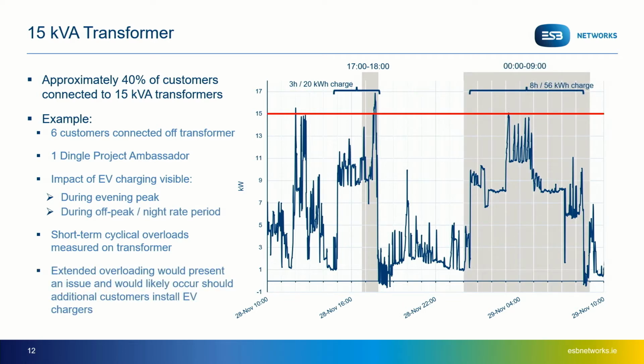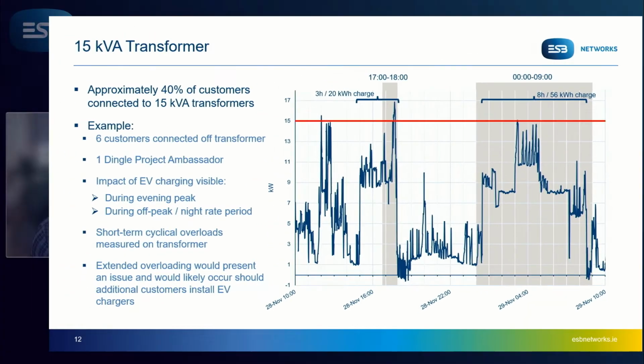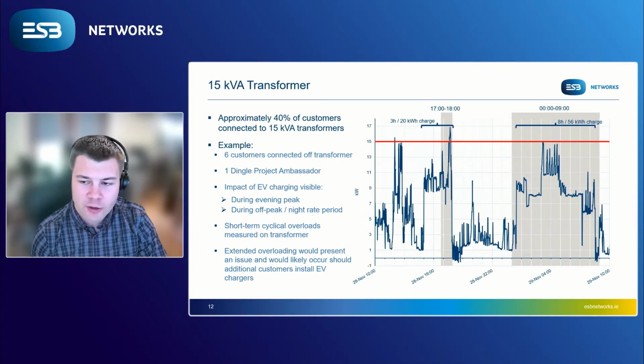Later on, we can see charging started again around midnight and lasted for approximately 8 hours until 8:30 in the morning. Across the trial, this is more common, as many participants are on day-night tariffs and are maximising savings by charging during that window, again highlighted here in grey. In this case, the loading on the transformer is high but remains just below the transformer rating, but it's clear that extended overloading would present an issue if additional customers on this transformer were to install EV chargers.